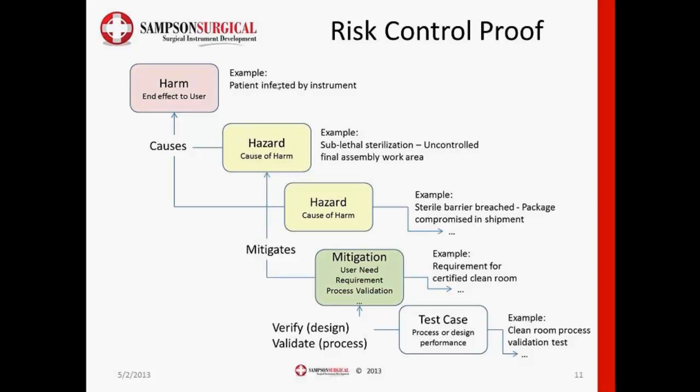But it's really a powerful tool for layering in all the different hazards associated with a particular thing. And as an example of documents we're going to need, if it's an ISO submission or a tech file submission, you're going to end up with a micro review of the sterility chain. You could identify each one of these with an attribute saying it's part of the sterility chain, and it would be easy to then sort the product requirements document or the hazard analysis specific to that cause, which is a real time saver.